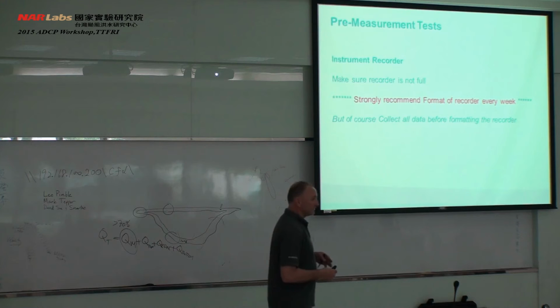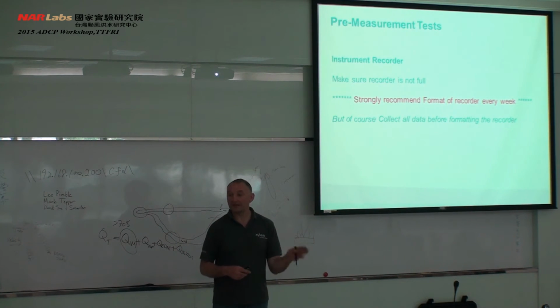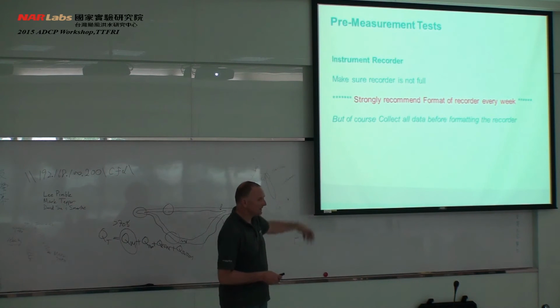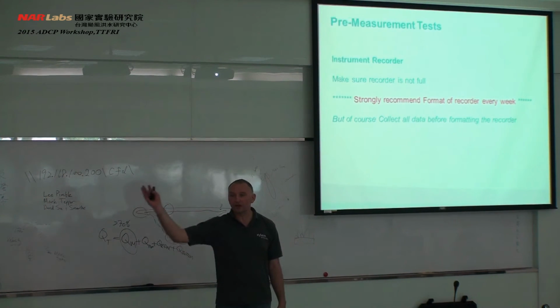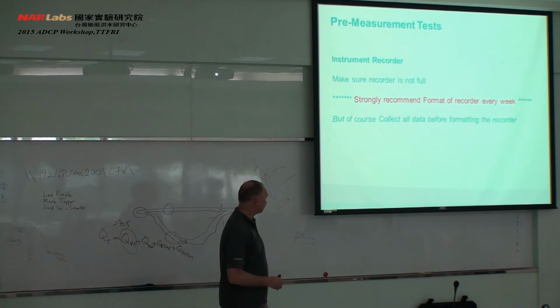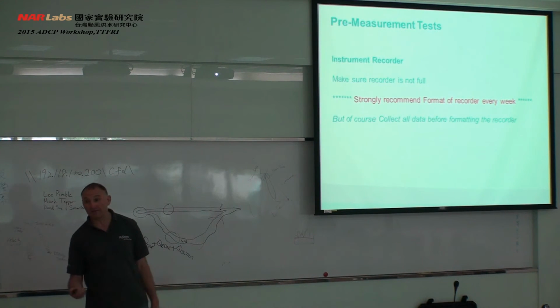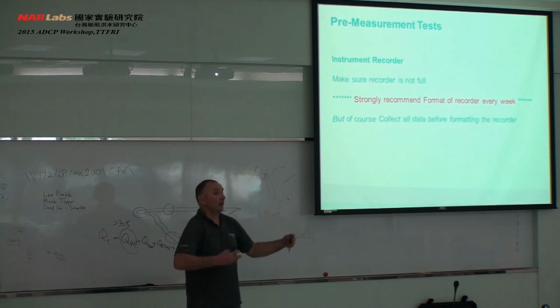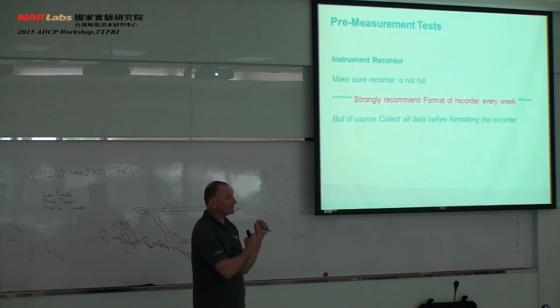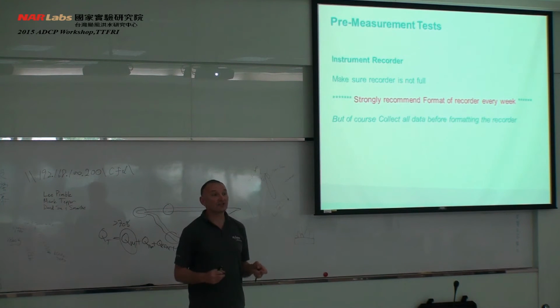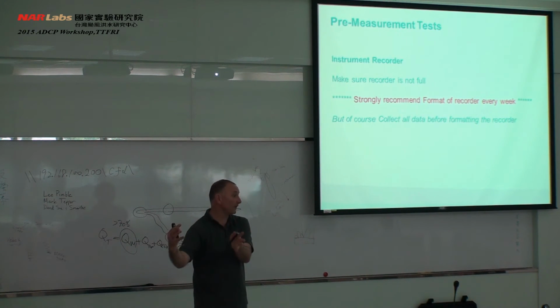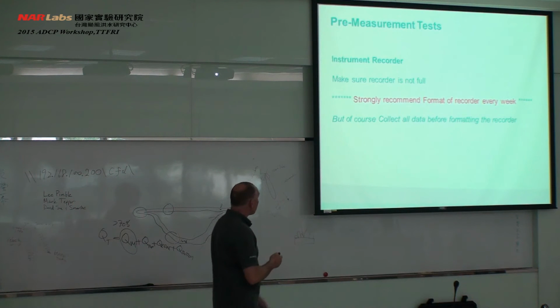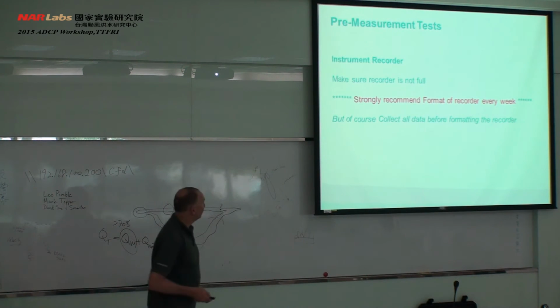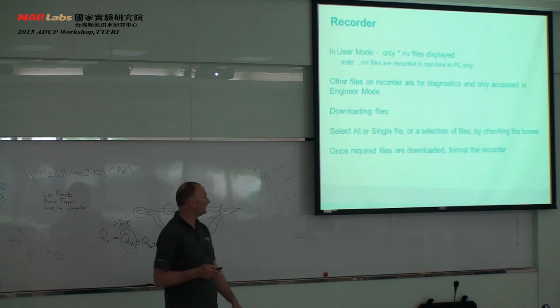So you might think you've got an empty recorder or plenty of room, but once you format it, it clears all those diagnostic files away, and then we can start getting quite confident. Those diagnostic files are there for good reasons. If you do have a problem with the instrument, don't format it. We can send the instrument back, and the engineers back in San Diego can look at the diagnostic files on the instrument to get a hint as to what's been going wrong. But of course, don't format your recorder until you've downloaded your data.